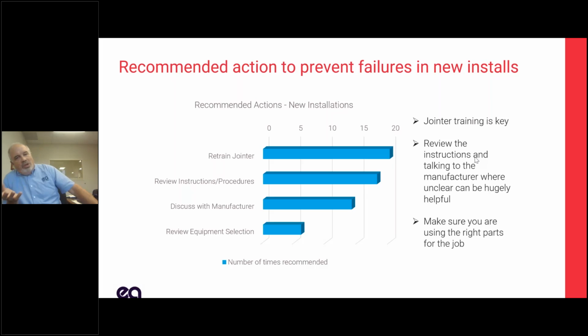What can we do about it? Well, we've got new installations. And obviously, if workmanship is the biggest problem, then you've got to make sure your jointers are well trained. You've got to have good instructions. You can't rely on the 4-pager that came with the cable termination kit and say, here, do this. No, you need detailed procedures. You might want to talk to the manufacturer of either the cable or the accessories and say, we're having these failures. What are we doing wrong? What can we do? Or change your equipment selection. If you don't have a really good system in place for doing hot shrink terminations, maybe you switch to cold shrink instead of doing hot shrink wrong. You really want to give this some thought when you're doing new installations.